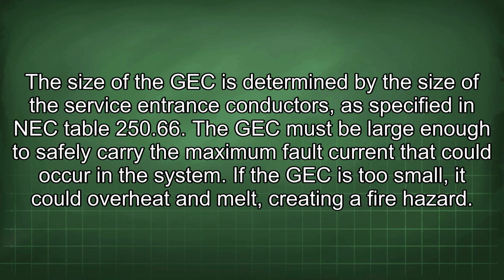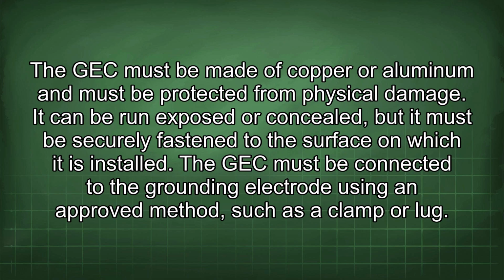The size of the GEC is determined by the size of the service entrance conductors, as specified in NEC Table 250.66. The GEC must be large enough to safely carry the maximum fault current that could occur in the system. If the GEC is too small, it could overheat and melt, creating a fire hazard. The GEC must be made of copper or aluminum and must be protected from physical damage. It can be run exposed or concealed, but it must be securely fastened to the surface on which it is installed. The GEC must be connected to the grounding electrode using an approved method, such as a clamp or lug.